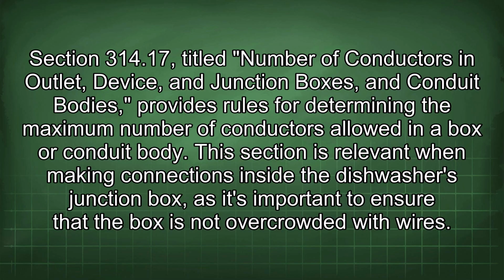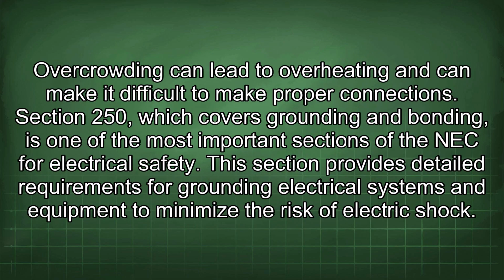Section 314.17, titled Number of Conductors in Outlet, Device, and Junction Boxes and Conduit Bodies, provides rules for determining the maximum number of conductors allowed in a box or conduit body. This section is relevant when making connections inside the dishwasher's junction box, as it's important to ensure that the box is not overcrowded with wires. Overcrowding can lead to overheating and can make it difficult to make proper connections.